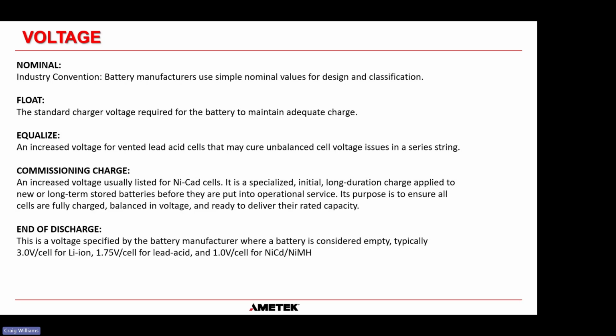Commissioning charge is an increased voltage usually listed for NiCad cells. It's a specialized initial long duration charge applied to new batteries, or batteries that have been stored for a very long time before being put into operational service. Its purpose is to ensure that all the cells are completely and utterly fully charged, balanced in voltage, and ready to deliver at their rated capacity.